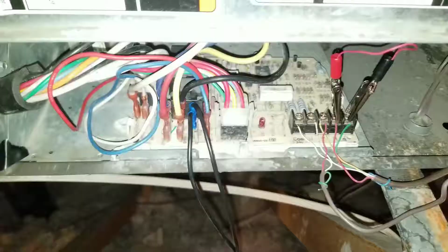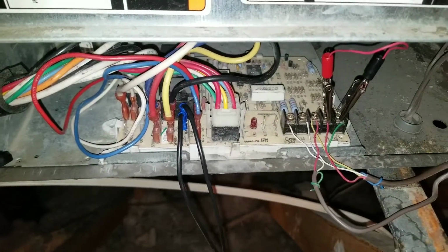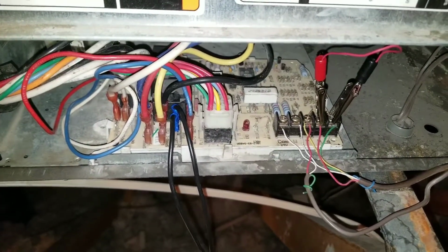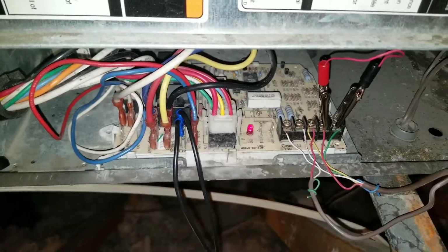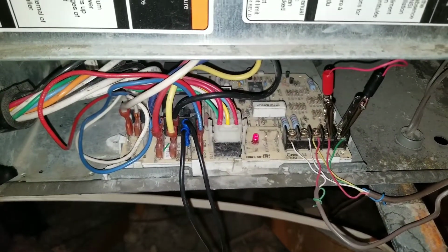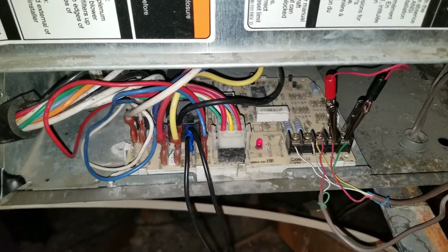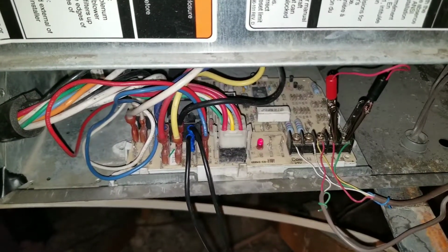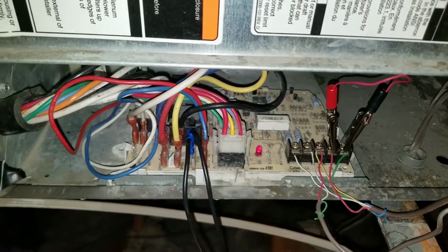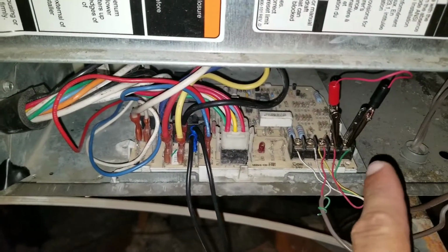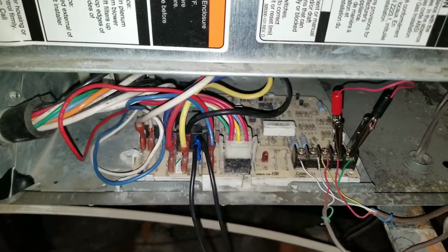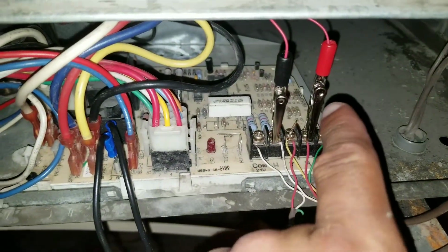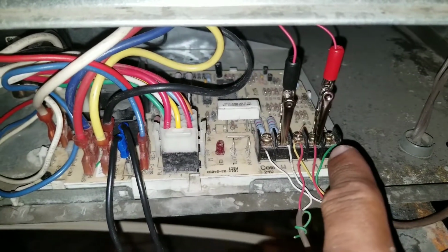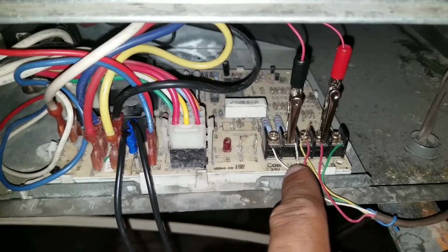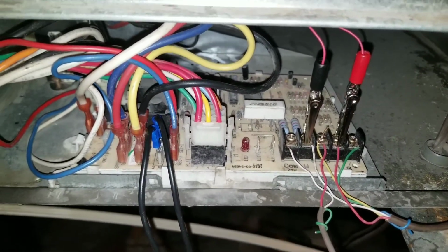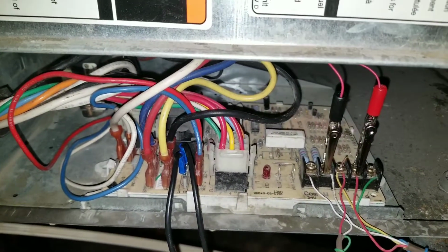Now I jumpered my blower motor. I'm going to turn the system on here from my circuit breaker. I turn the switch on, and right now my blower should engage. Now I'm going to turn my switch off, and I'm going to move my jumper from my blower to my heat. Here I have my alligator clip on my R, that's my 24 volts, and on my W terminal, which is going to be my heat, I'm going to turn the system on, and the heater should turn on.